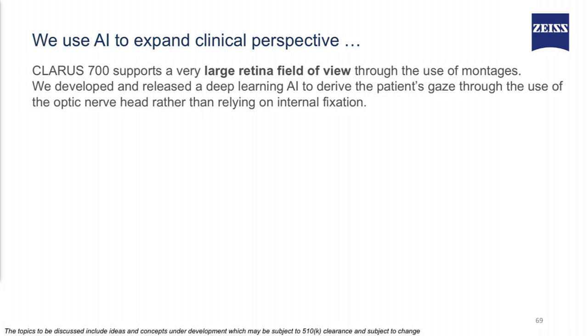We use AI to expand the clinical perspective. The CLARUS 700, which got FDA clearance recently, supports a very large field of view through the use of montages. We developed and released a deep learning algorithm to create these montages. Traditionally, montages are created by relying on the patient's gaze. We cannot rely on the patient's gaze when we look at the aging population, so we introduced an algorithm which can automatically derive the patient's gaze and create the beautiful montages which you are seeing on the screen.